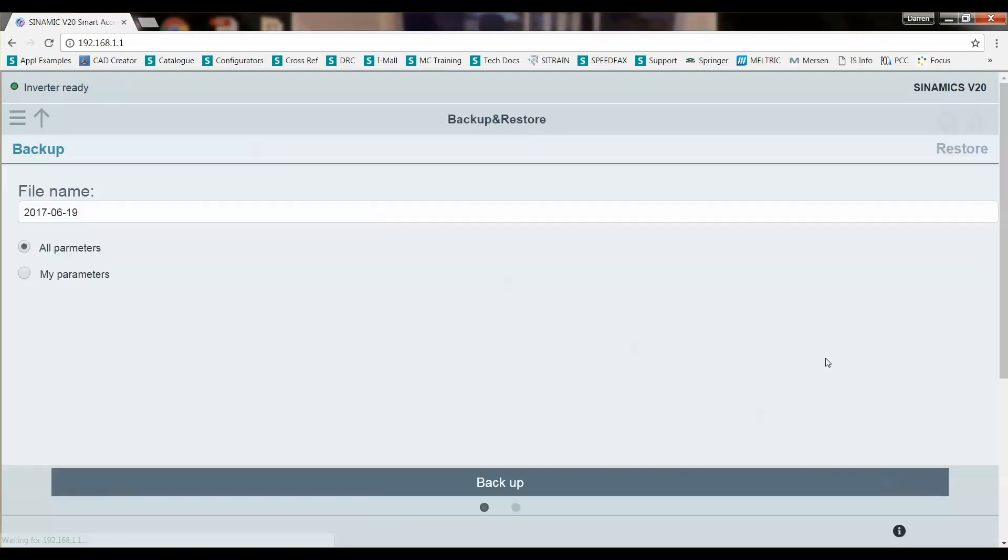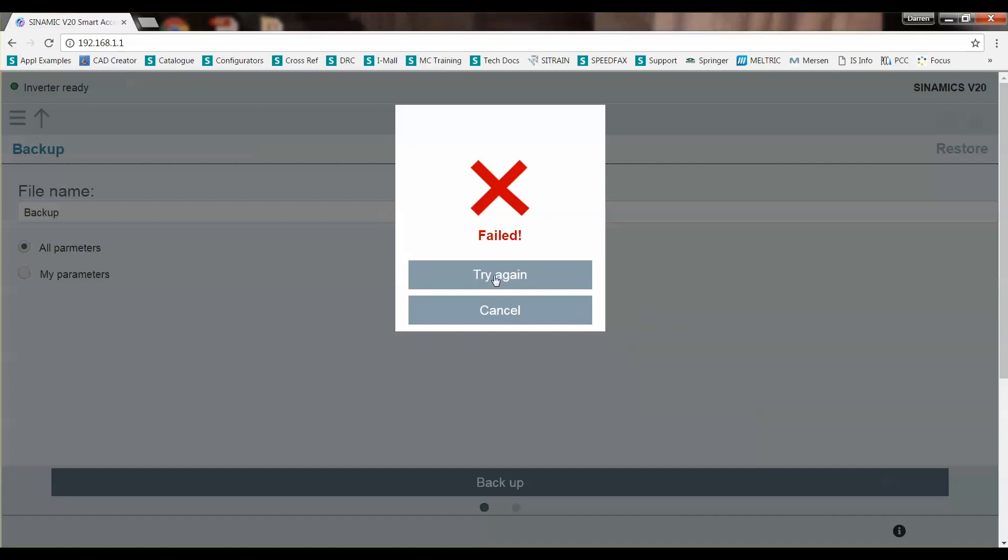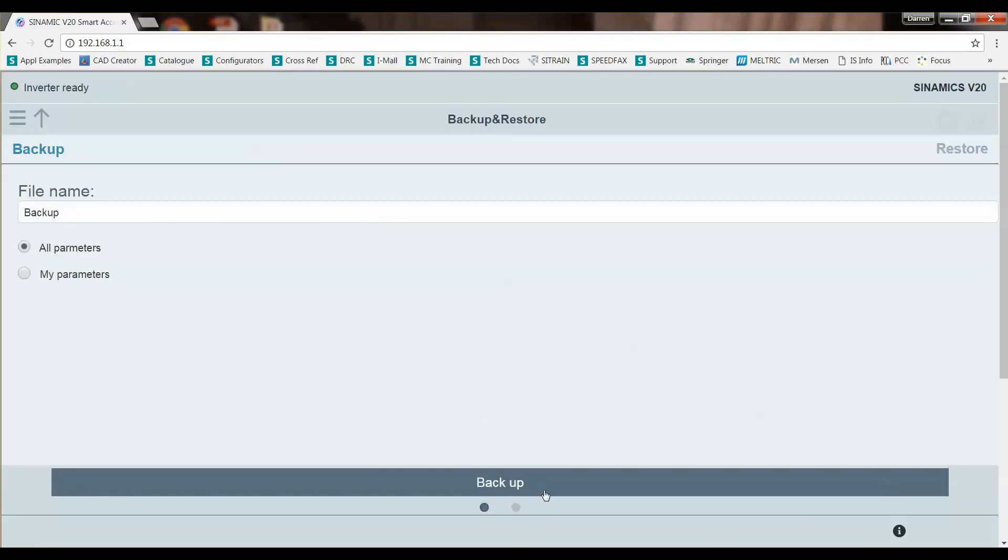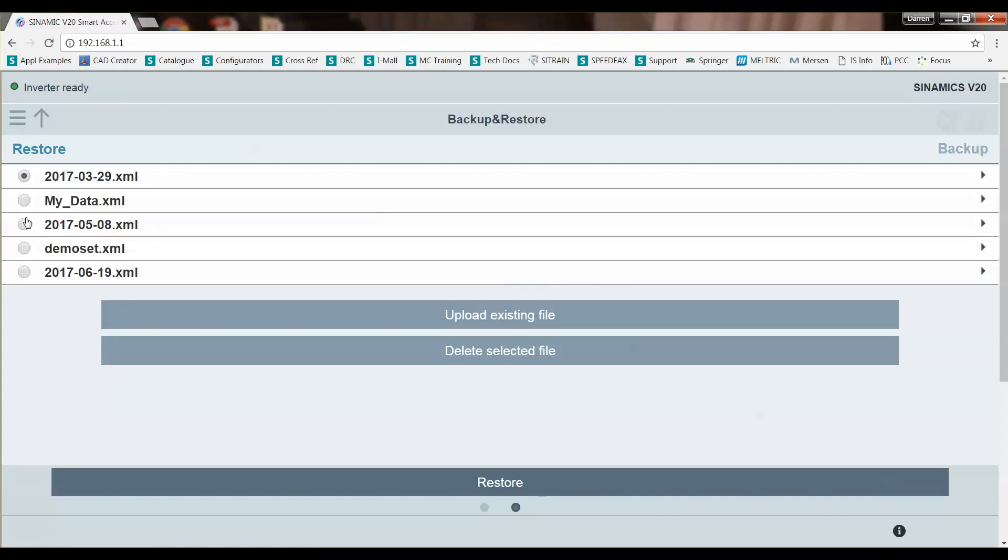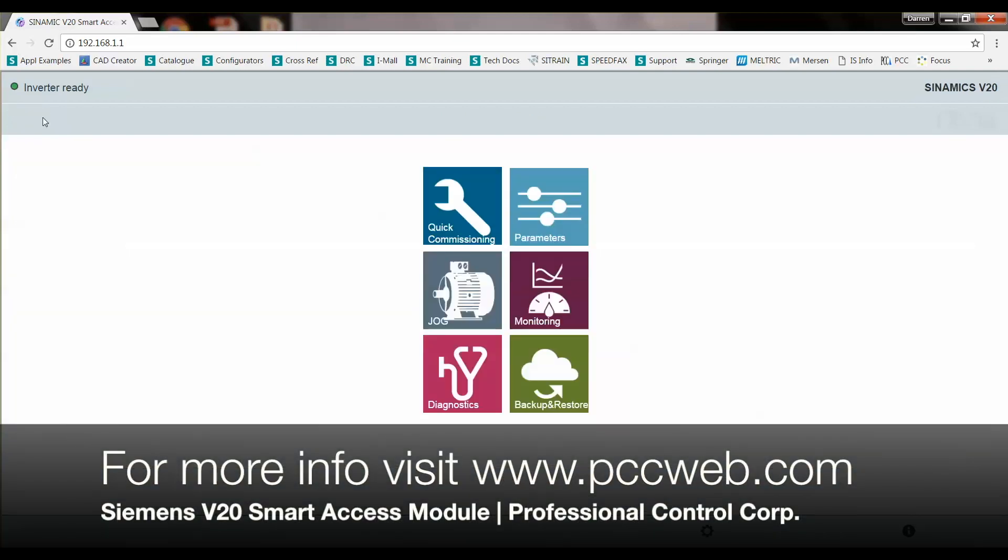And lastly, we can backup and restore parameters. So if I want to call this the backup, you can click backup and it's going to backup the file set. I'm not going to wait for it to do it. And if I want to restore, I can go next and I can choose another set and restore that data set. I can use that to either restore this drive if it ever fails or to copy parameter sets to different drives by putting a smart access module on another drive and clicking restore and it'll just download that parameter set to that new drive. So that is a quick overview of the smart access module. Thank you.